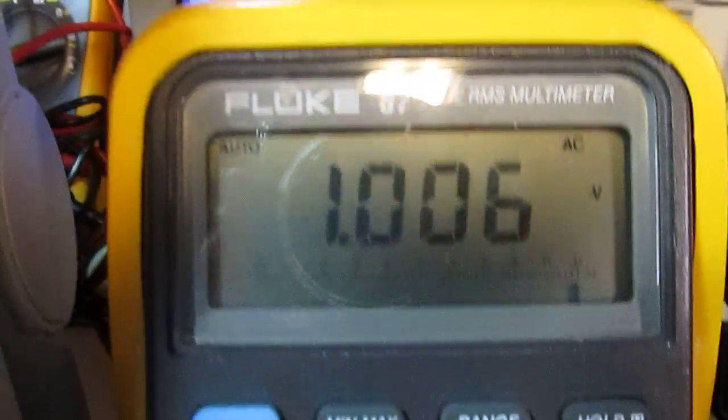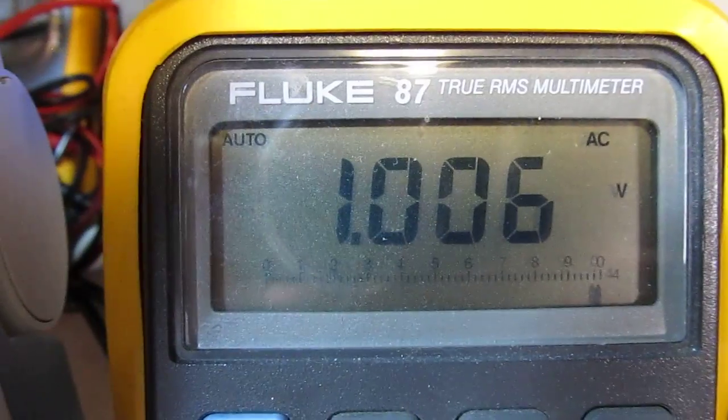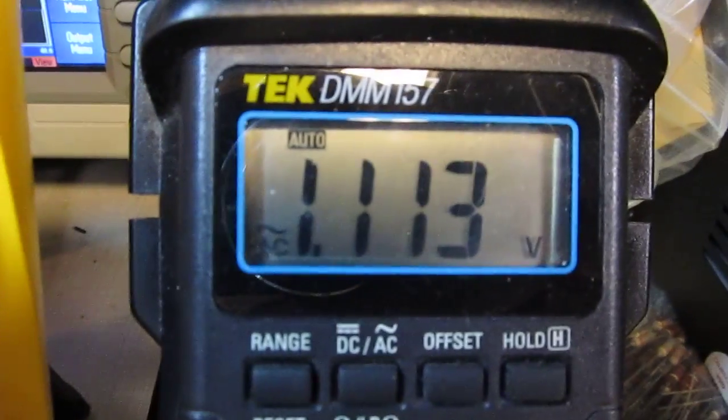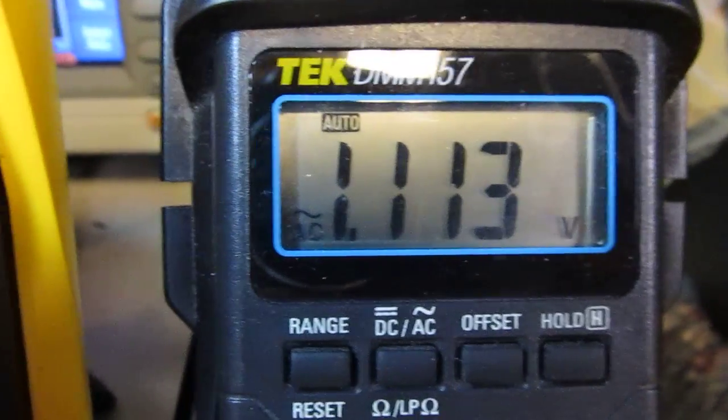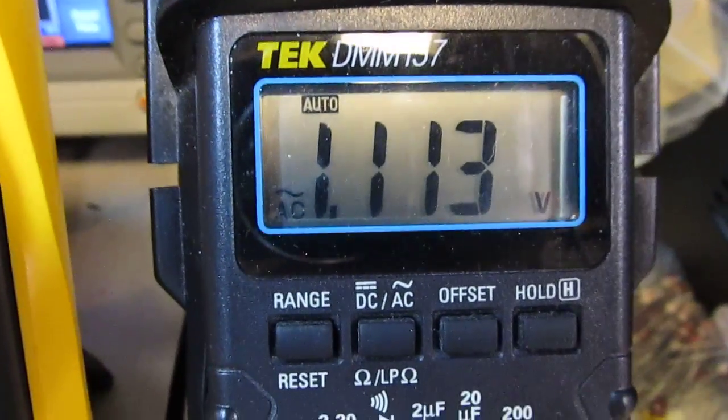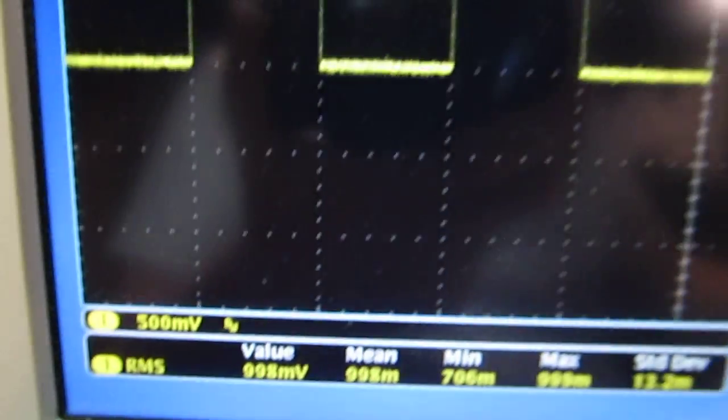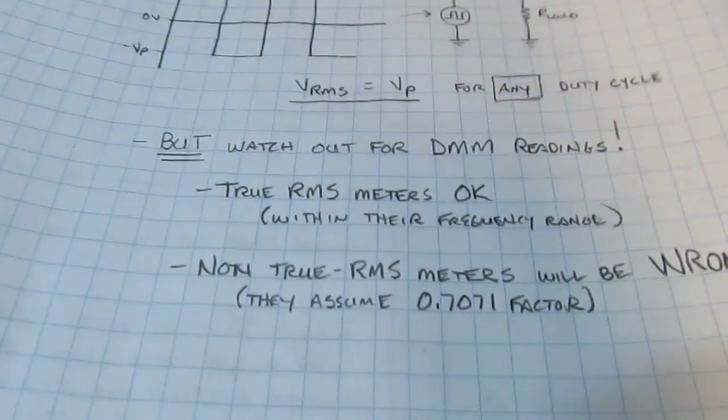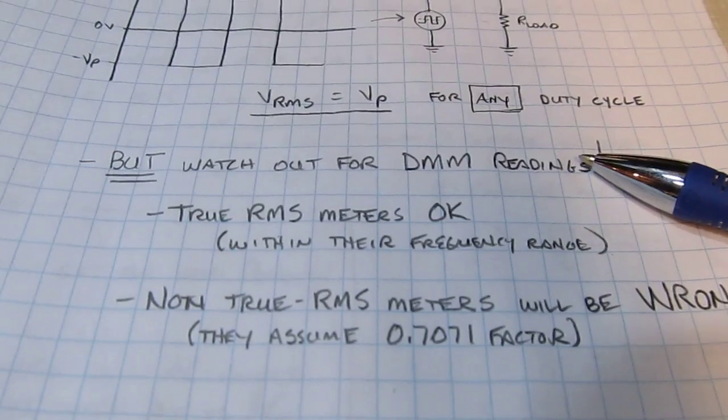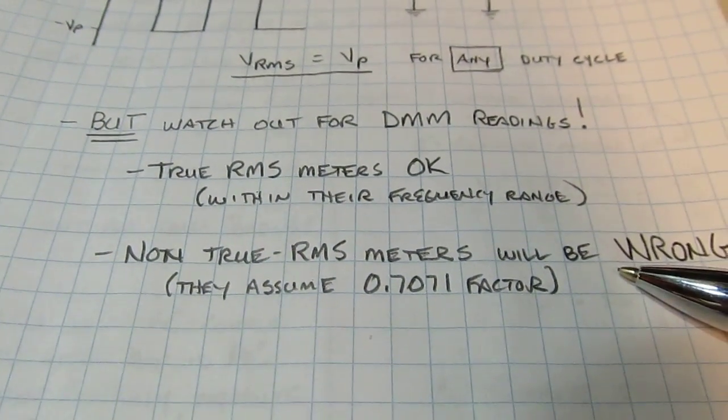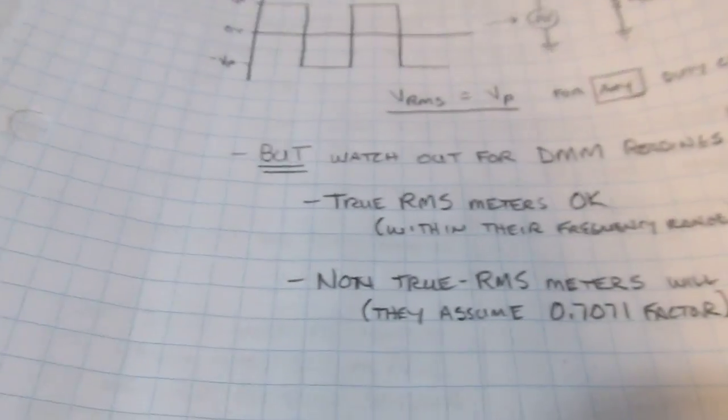And we can see that here. I've got that same 2 volt peak to peak. My true RMS reading multimeter reads at about 1 volt, which is what it should, because this is going between plus and minus 1 volt. So that's reading that. But the non-true RMS reading meter is not reading it correctly. That's reading a little bit high because it's improperly using that 0.707 factor, because this signal is not a sine wave. If we look at the scope, it's a square wave centered around 0. And if we look at the reading down here, we can see that that is reading just about 1 volt as well. So the scope is doing it right. The true RMS meter is reading it correctly. But the non-true RMS reading is not. So the caution here is to watch out for DMM readings. True RMS meters will read fine, but non-true RMS readings will be wrong because they assume that 0.707 factor.